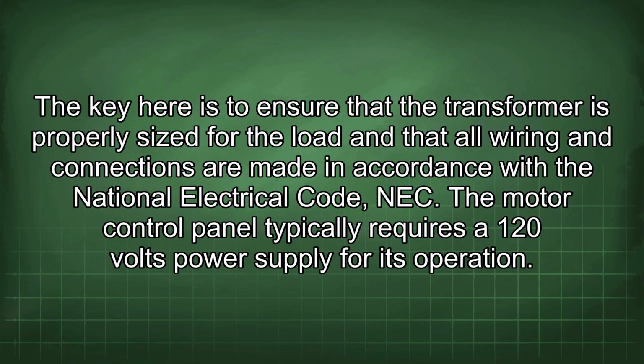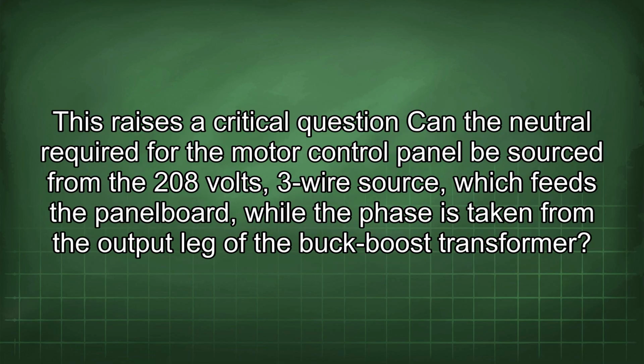The motor control panel typically requires a 120 volts power supply for its operation. This raises a critical question: can the neutral required for the motor control panel be sourced from the 208 volts 3-wire source which feeds the panel board, while the phase is taken from the output leg of the buck-boost transformer?